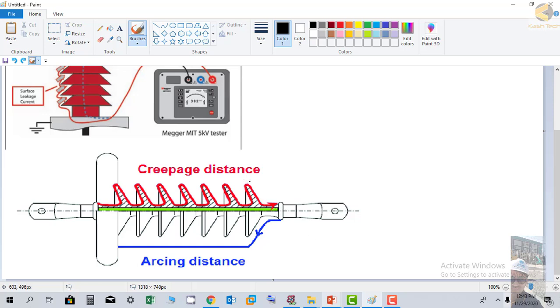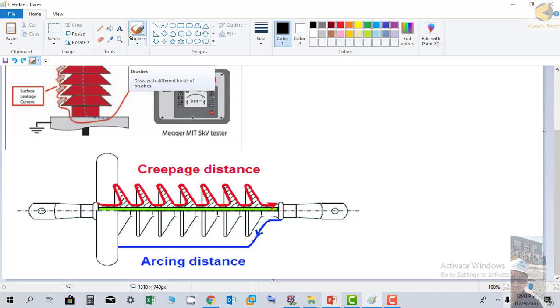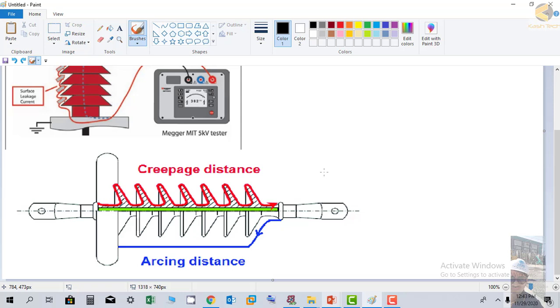A small amount of current will flow through or over the surface of the insulator, following this path to ground. This current will be added to the conduction current and will reduce the reading, depending upon if someone is testing the equipment.